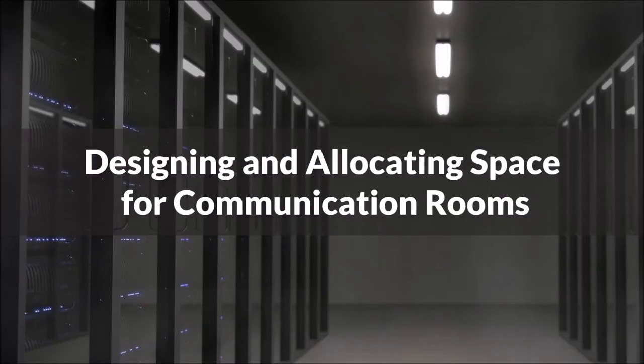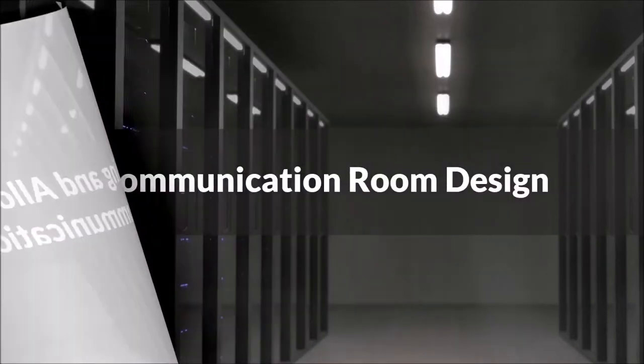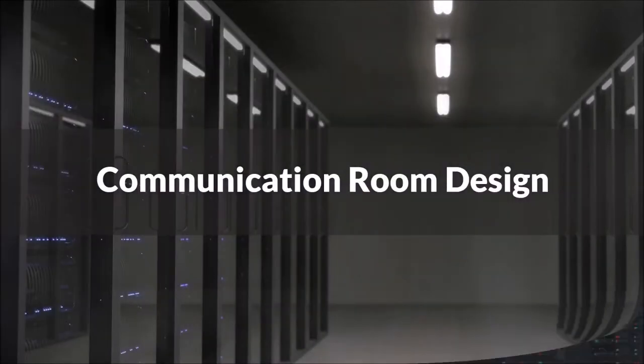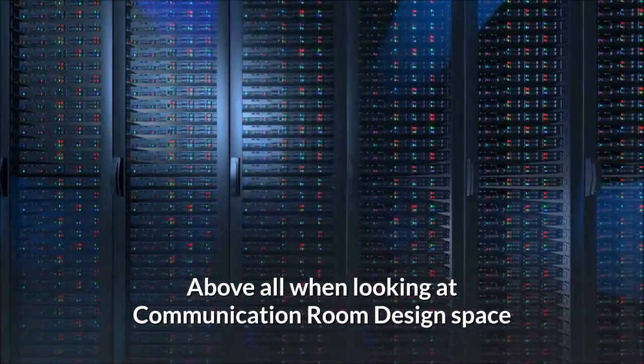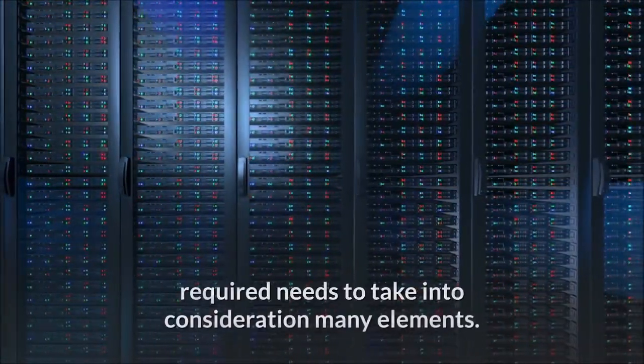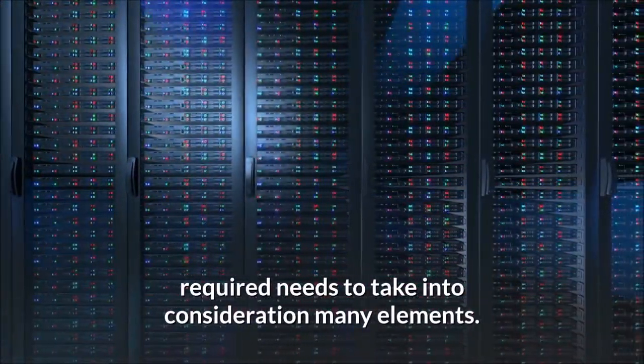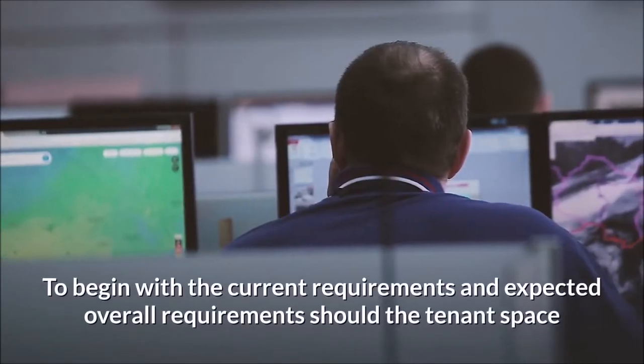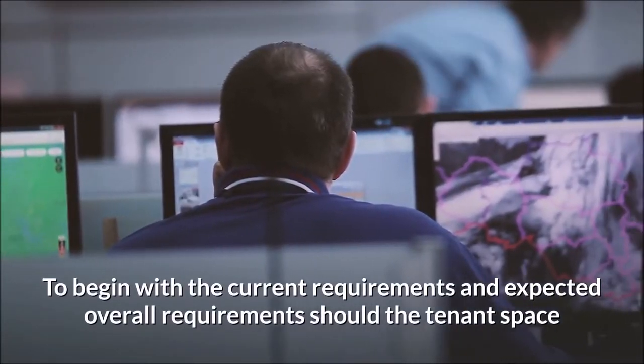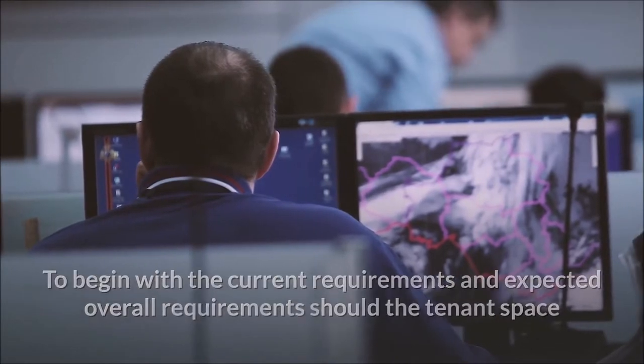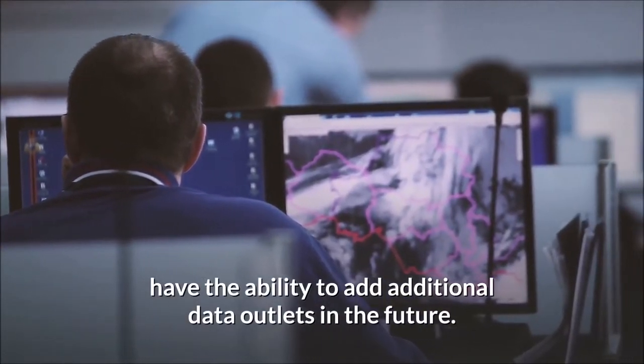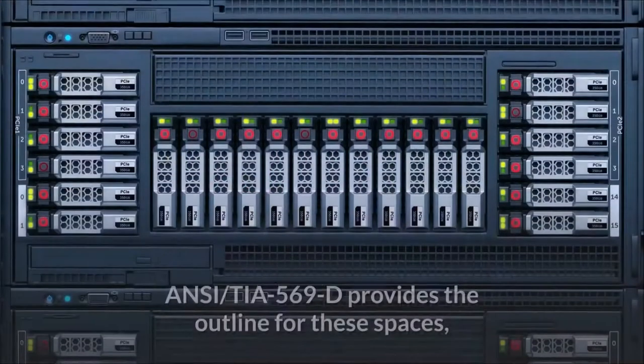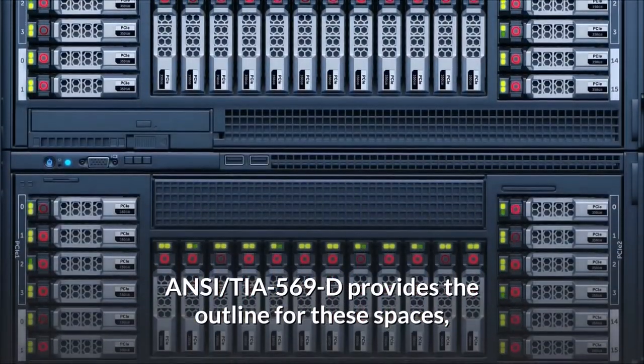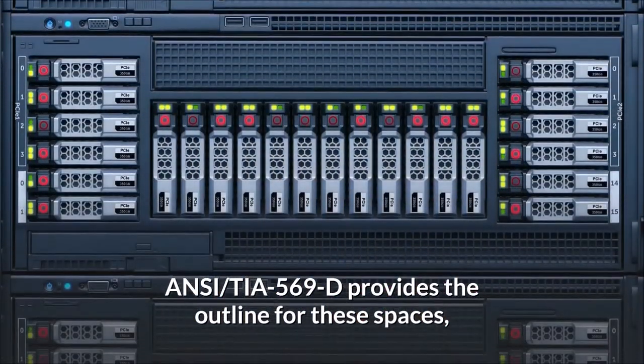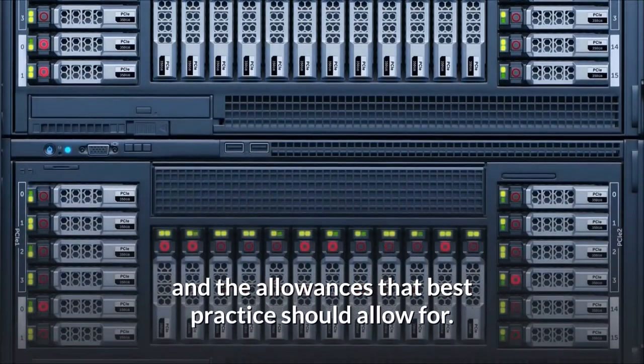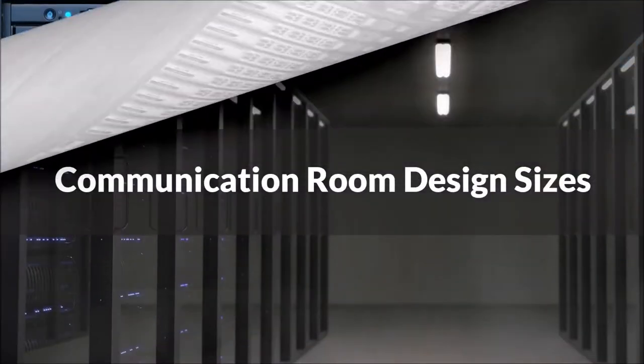Designing and allocating space for communication rooms. Communication room design. Above all, when looking at communication room design, space required needs to take into consideration many elements. To begin with, the current requirements and expected overall requirements, should the tenant space have the ability to add additional data outlets in the future. ANSI TIA 569D provides the outline for these spaces, and the allowances that best practice should allow for.